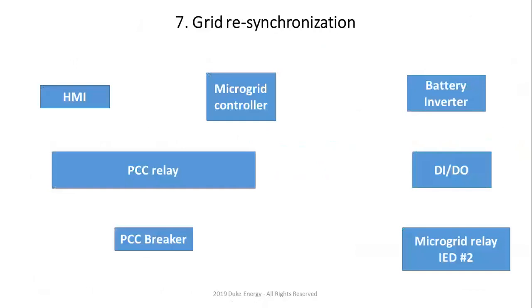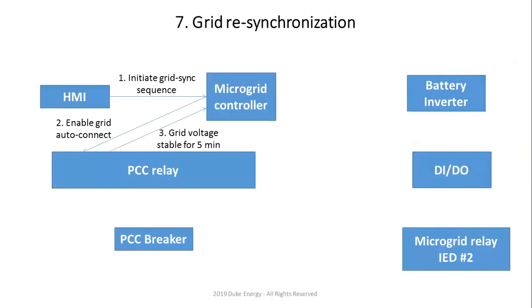Now, seamless grid resynchronization. Remember, if you have Y grounded Y transformers on your DERs, you need that grounding transformer. Without the grounding transformer, you won't be able to synchronize because your PCC relay is going to block it, right? So the way we do this, we essentially initiate the grid synchronization sequence. Our microgrid controller enables the grid auto connect, which means that we want to make sure we have a healthy voltage on the feeder, that it's not just coming in and out, right? When the PCC relay says, yeah, I have stable voltage for 5 minutes, we start the grid sync procedure.